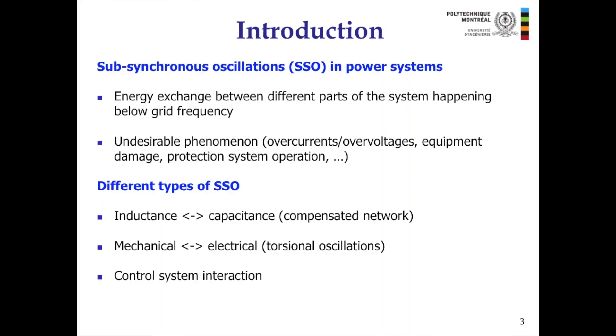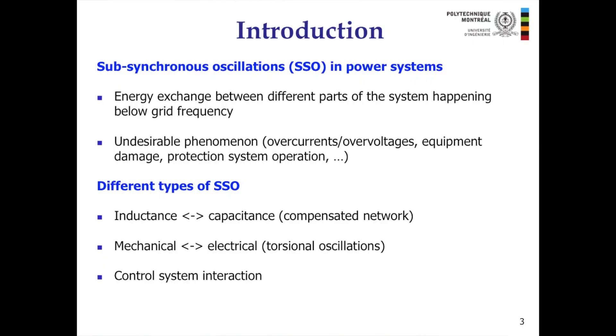As a brief introduction, sub-synchronous oscillations in power systems is generally an energy exchange between different parts of the system that happens below the grid frequency. It is usually an undesirable phenomenon because it can cause overcurrents, overvoltages, equipment damage, protection system operation or misoperation, et cetera.